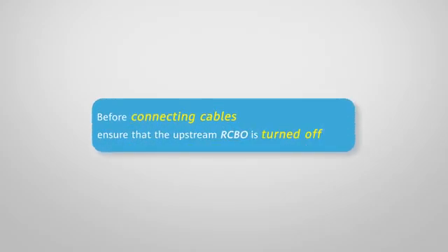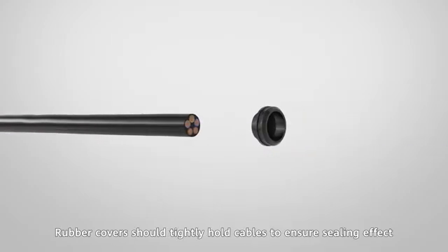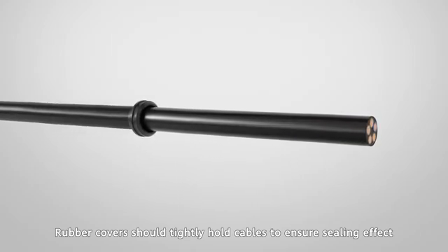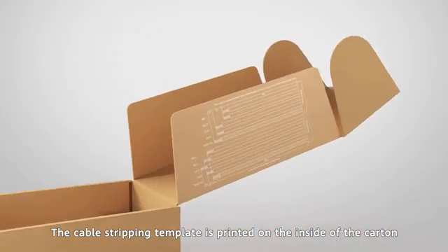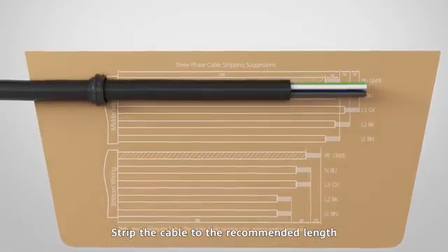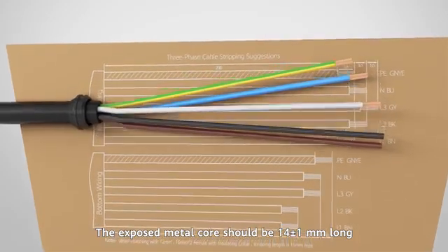Before connecting cables, ensure that the upstream RCBO is turned off. Use scissors to cut the rubber covers to fit the cable sides. Rubber covers should tightly hold cables to ensure a sealing effect. The cable stripping template is printed on the inside of the carton.